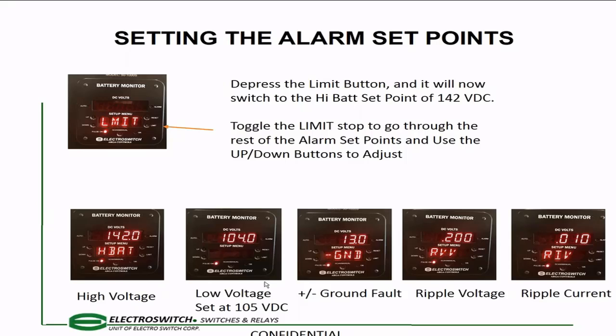Then I go to my low voltage. It doesn't show my low voltage, but that's what it says. It'll be LBAT, and then I use my up and down arrow. The low voltage is typically set at 105 volts DC. I have my positive ground and negative ground, and I set that at 13 volts. That's what it comes out as from the factory.